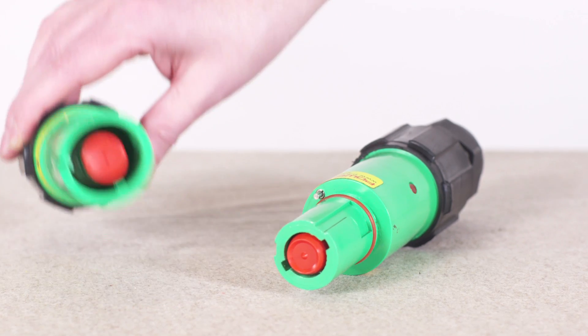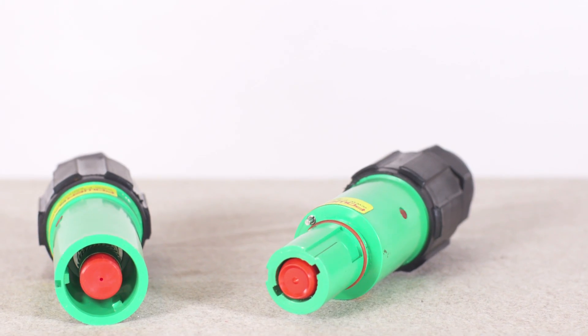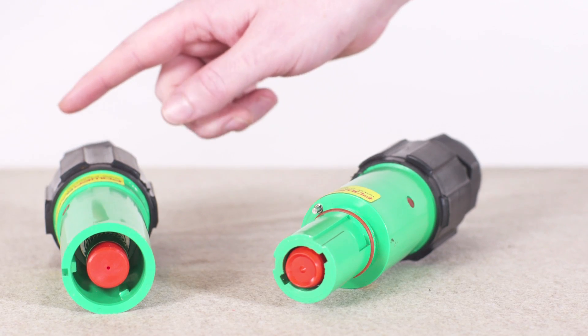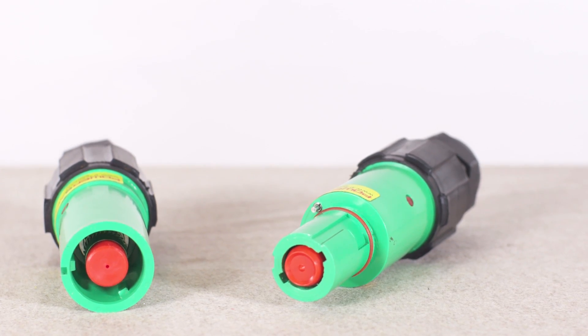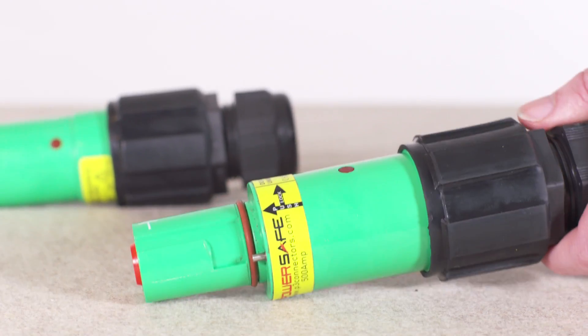PowerSafe connectors are designated as source or drain. The source connectors are intended to have their permanent connection in the direction of the source of electrical energy and the drain connectors are intended to have their permanent connection in the direction of equipment receiving power.